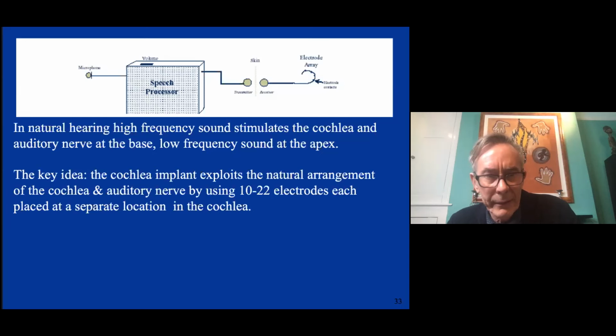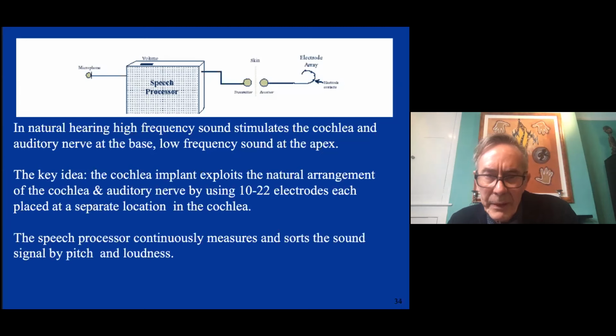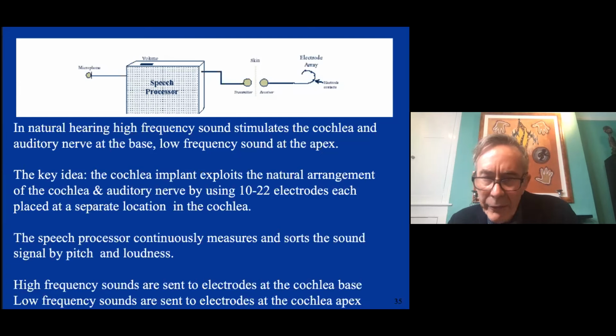So the key idea with the cochlear implant is to exploit the natural tonotopic arrangement of the cochlea and auditory nerve by using typically 10 to 22 electrodes, each placed at a separate location of the cochlea. And then the speech processor continuously measures and sorts the sounds by pitch and by loudness. And the high frequency sounds are sent to electrodes in the form of electrical currents at the cochlear base, and the low frequencies are sent to electrodes at the cochlear apex.